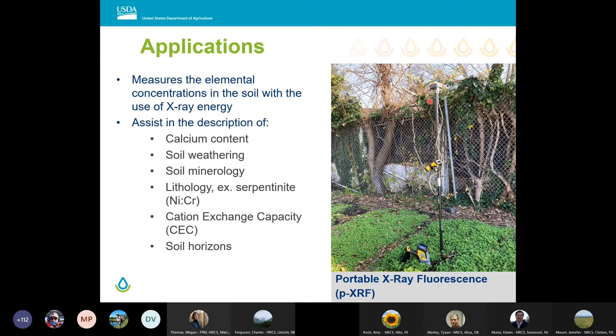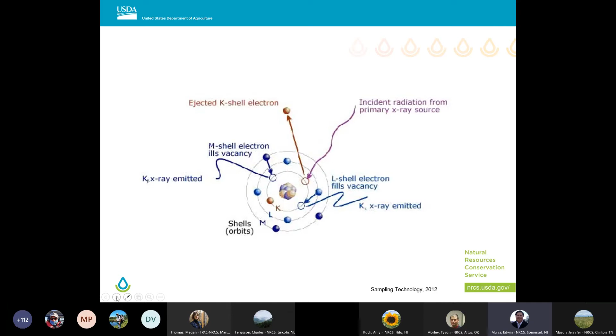So how does this work? The way that this works is X-ray energy excites some of the electrons in lower orbits, and those electrons shoot out of the orbits, resulting in electrons from an upper orbit moving to the lower orbit. As you can see here, that movement generates energy. That energy is fluorescence, and every element generates its own energy, characteristic with a wavelength, if you will. So the equipment picks up that fluorescence and the amount of it, and then it can produce an output. In this case, it could be parts per million or percent, depending on the concentrations and also on the equipment.